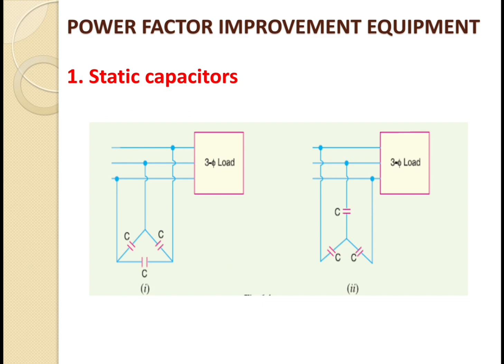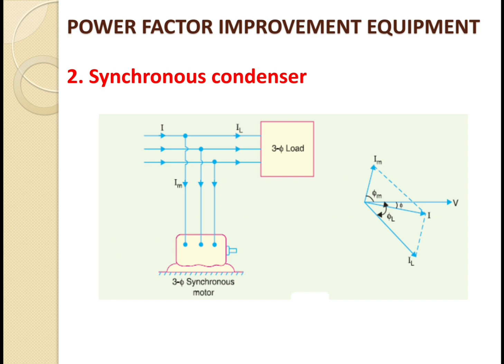We have finished the Static Capacitor. Now we will go for the second equipment used for power factor improvement, which is known as the Synchronous Condenser. A synchronous motor which takes a leading current when over-excited can behave as a capacitor. An over-excited synchronous motor running on no load is known as a Synchronous Condenser.